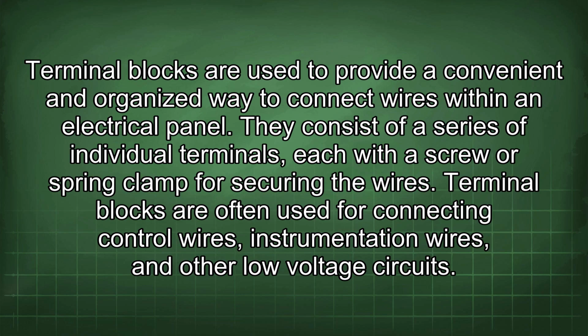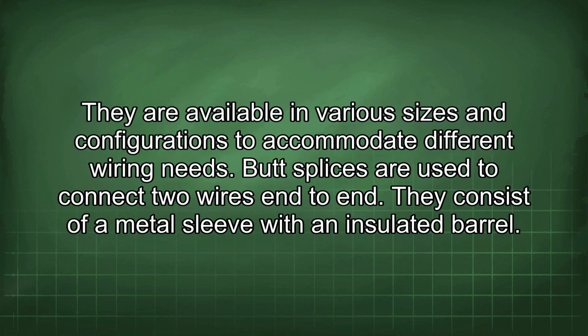Terminal blocks are used to provide a convenient and organized way to connect wires within an electrical panel. They consist of a series of individual terminals, each with a screw or spring clamp for securing the wires. Terminal blocks are often used for connecting control wires, instrumentation wires, and other low-voltage circuits. They are available in various sizes and configurations to accommodate different wiring needs.